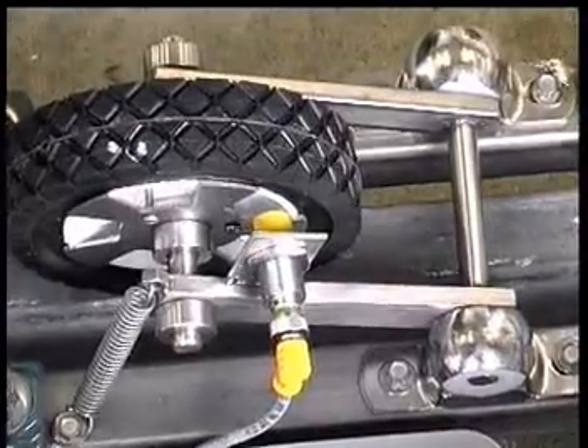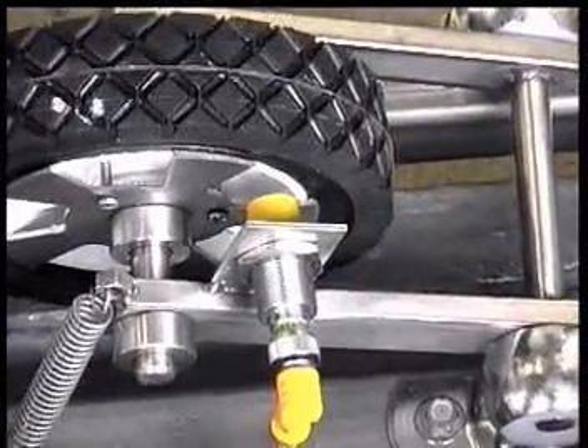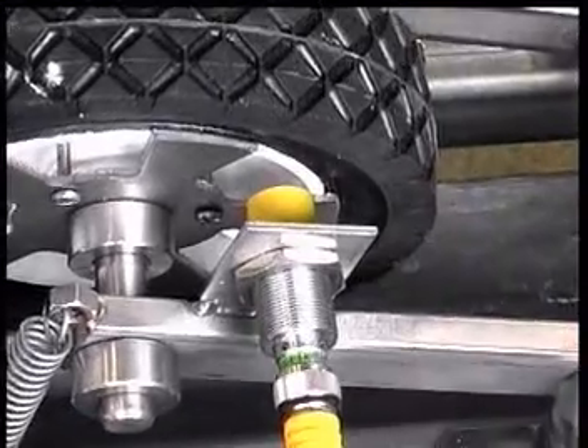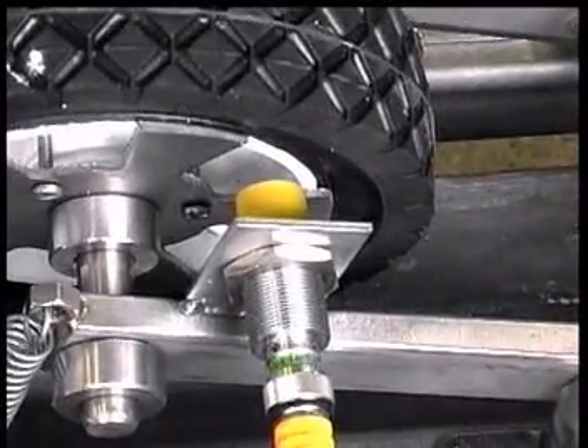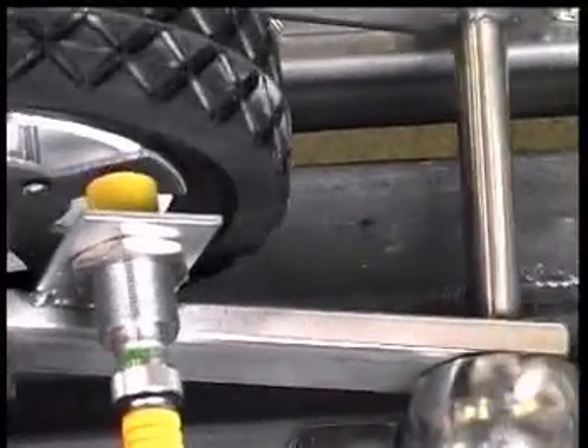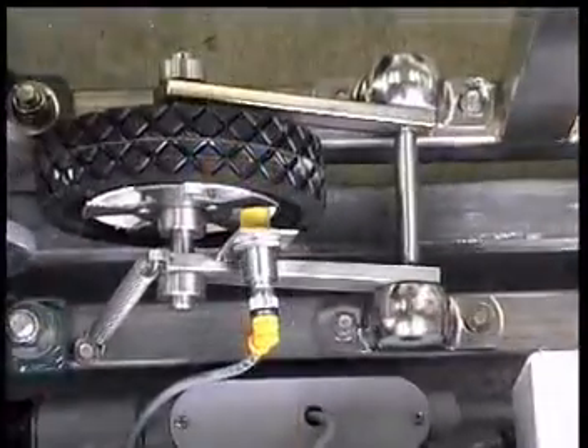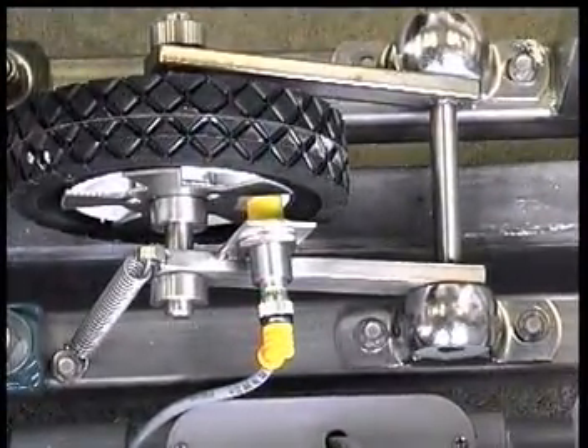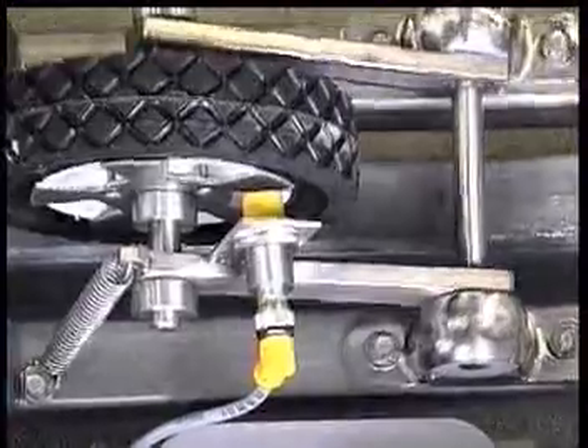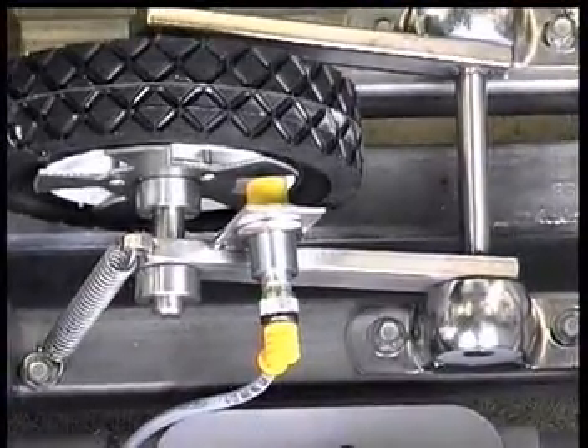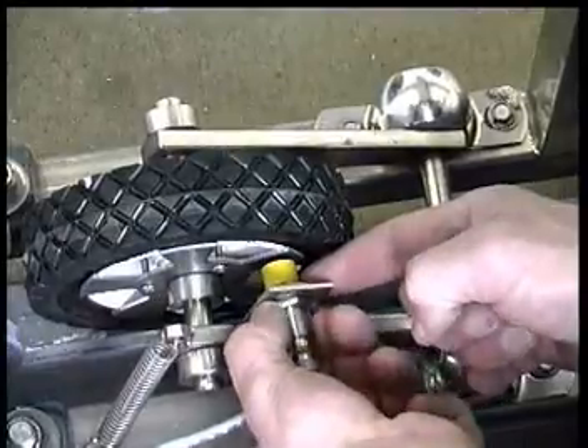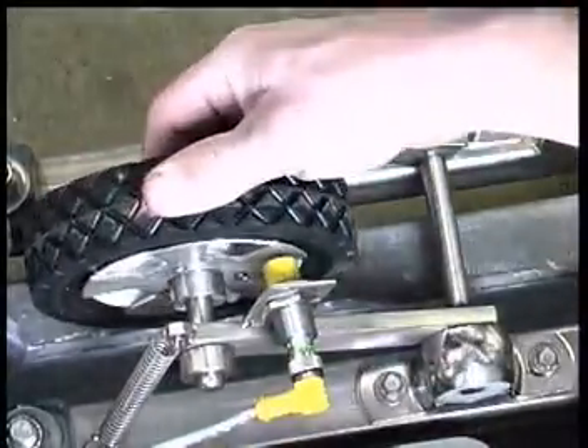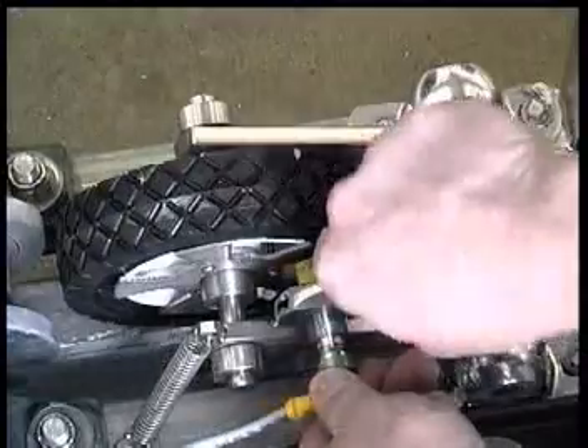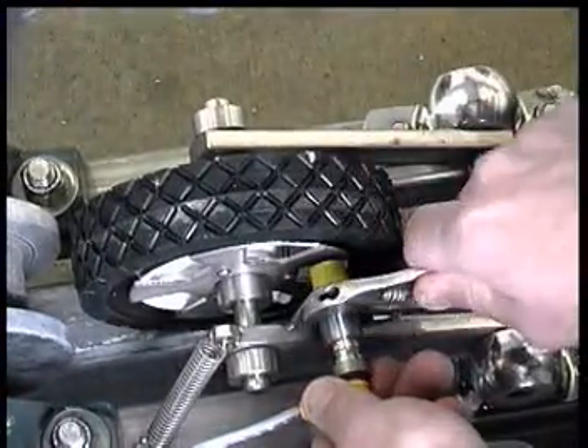A prox is an electrical switch that operates when metal is on or near the head of the prox. We refer to this metal as a prox target. Proxes used on the Water Wizard require a 1/8 to 1/4 inch clearance for proper operation. Any closer may damage the face of the prox. Any further away and the prox may not read its target. Adjustments are made using locking nuts on the threaded prox body. Locking nuts must be secure so the prox doesn't self-adjust.